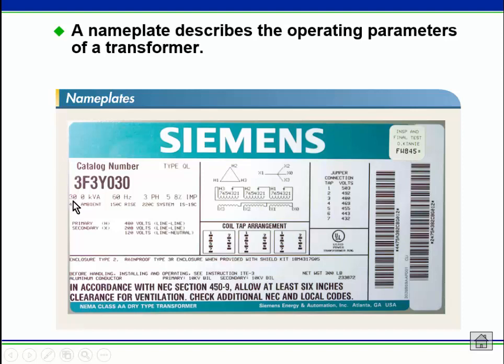Notice this is a 30 kVA transformer. That means you can put 30 kVA on it, on the primary and on the secondary. We kind of ignore the losses on these things. The impedance, 5.8% impedance. So we're going to use that number in some calculations we'll do in class, show you what that does, but impedance has to do with how you can figure out the maximum fault current that will flow through a transformer if you have a short.